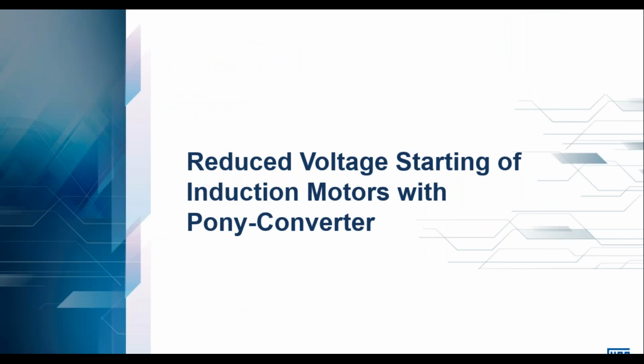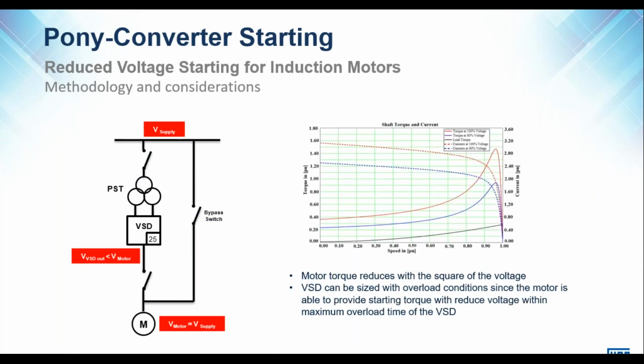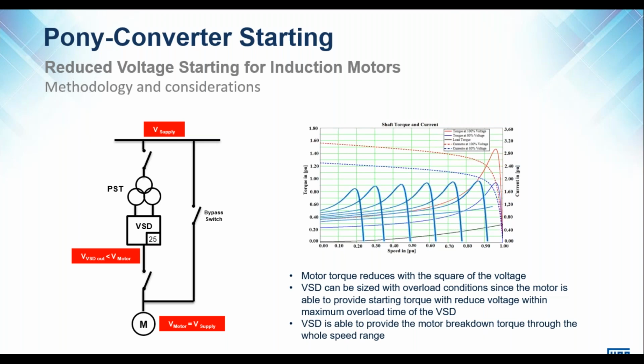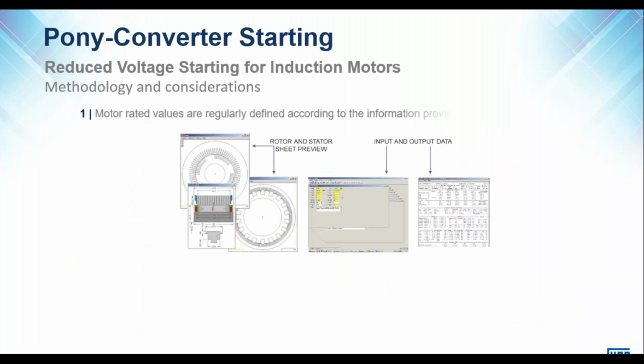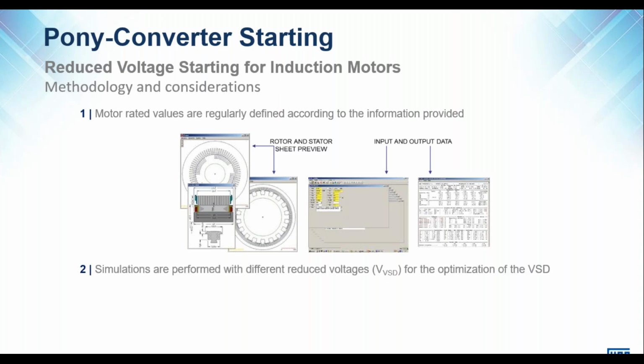Okay, so that was one example of optimizing a startup using a smaller drive, but rated at the same voltage. We can go one step further and actually start a machine with both a smaller rated VSD and a VSD with a lower voltage output than the supply voltage. Of course, there are a lot of design considerations that we need to take into account.